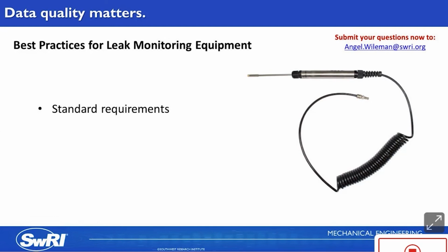Review these procedures carefully when selecting your leakage measurement equipment and performing the test. The standards will list requirements for the leakage detector, including the maximum response time, maximum recovery time, sample flow rate at the detector probe, and the maximum allowable variation or sensitivity of the instrument. Make sure the leak detector is calibrated over the tightness range that you are expecting, and this is especially true for the ISO testing since the tightness class can vary based on the qualification range.